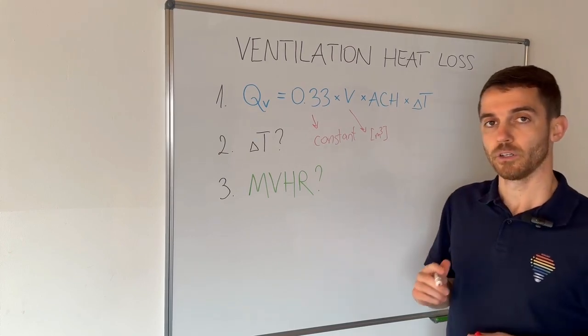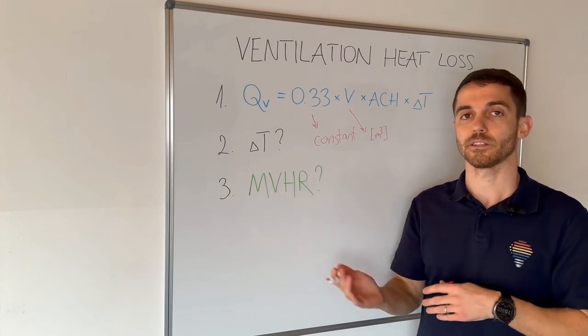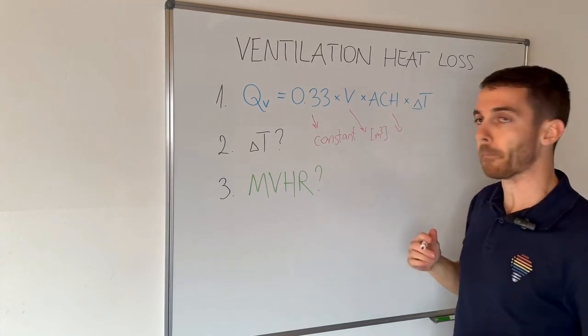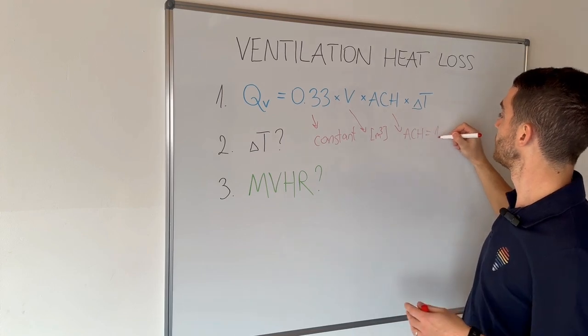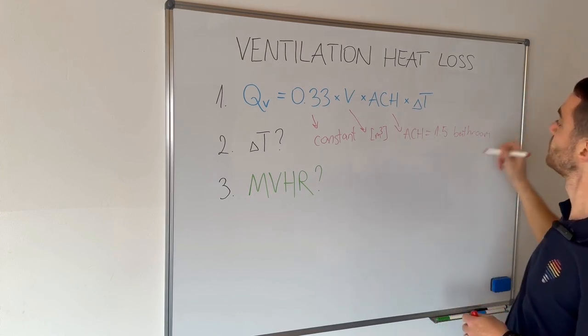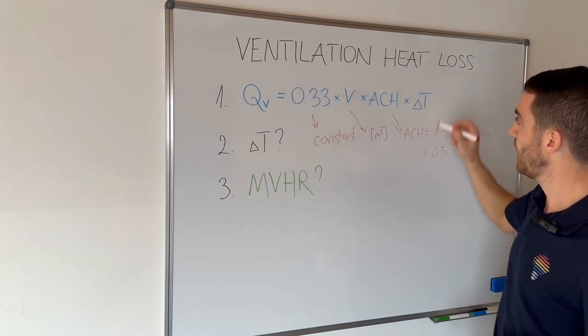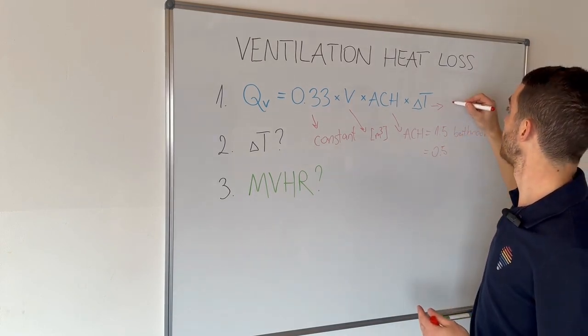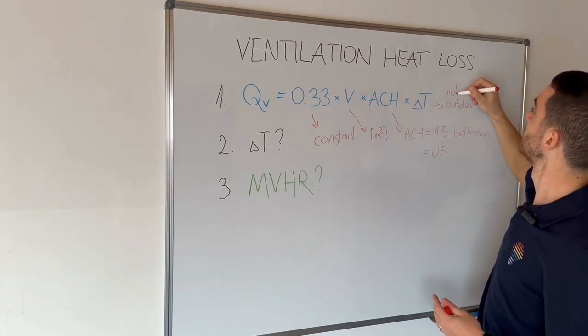Air changes per hour is usually calculated from formulas, legislation, and norms. In most countries, for example, air changes per hour in a bathroom is 1.5, and in other rooms it is 0.5. Delta T is the same as in fabric heat loss — the temperature difference between outdoor and indoor temperature.